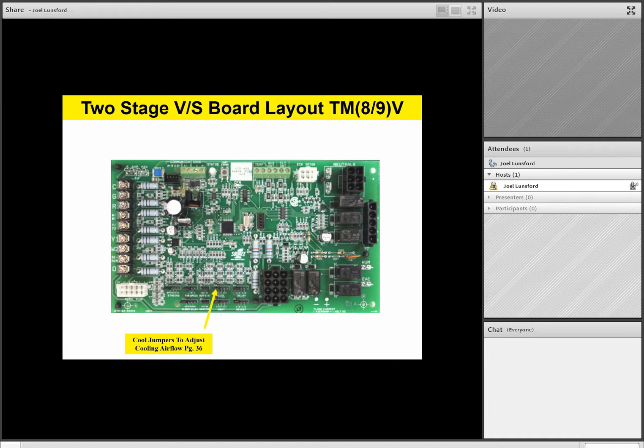We always want to set our airflow up in the cooling mode of operation with the cool and adjust jumper for 400 CFM per ton. So if I have a 2-ton unit sitting outside, I need to set my cool and adjust jumper up for 800 total cooling CFM on a 2-ton unit. If it's a 3-ton unit, it'd be 1200 CFM. If it was a 4-ton unit, it would be 1600 CFM, and so on. So we always set the cool and adjust jumper up for 400 CFM per ton of capacity of the outdoor unit. So the cool and the adjust, they work together for cooling airflow.